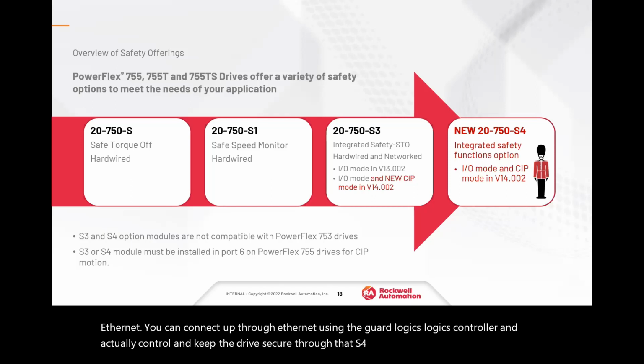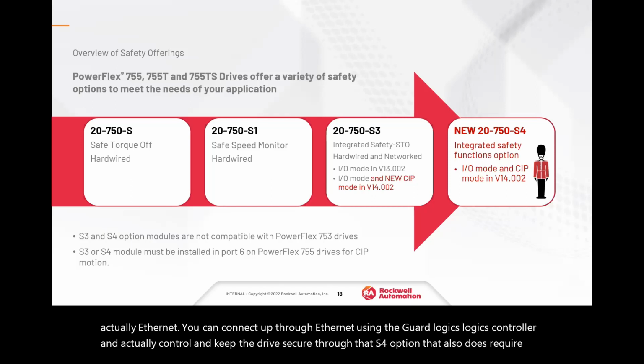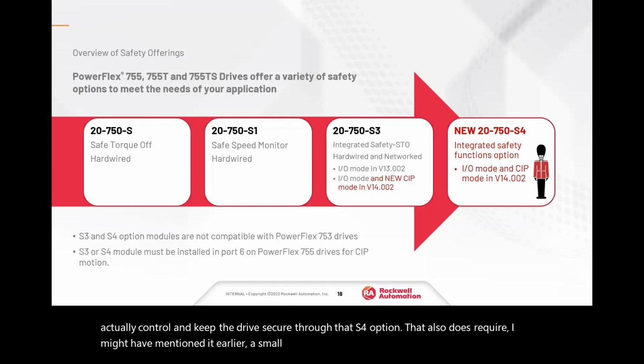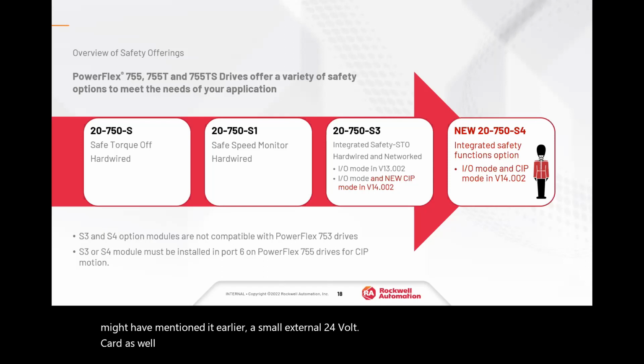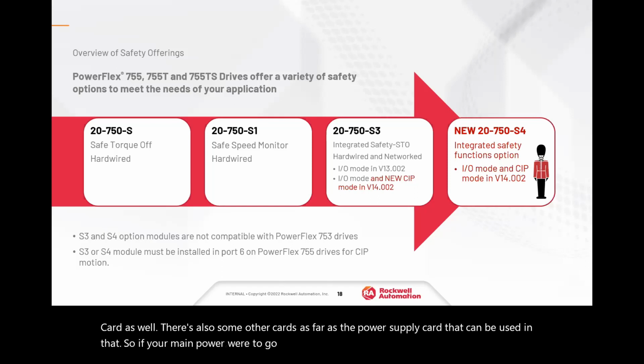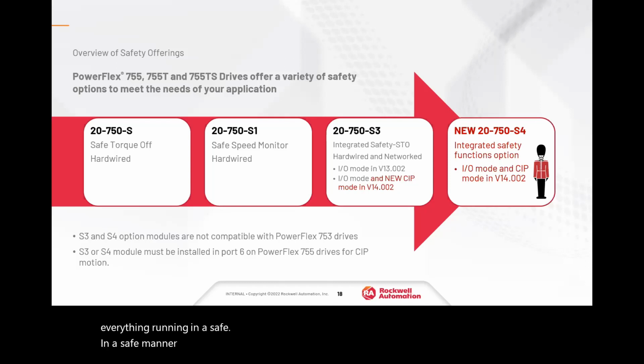That also does require, I might have mentioned it earlier, a small external 24-volt card as well. There's also some other cards, as far as a power supply card that can be used in that. So if your main power were to go down, you could actually shut the drive down and keep everything running in a safe manner using some of these features. Not only the S4 card, but also the additional slot mountable power supply card.